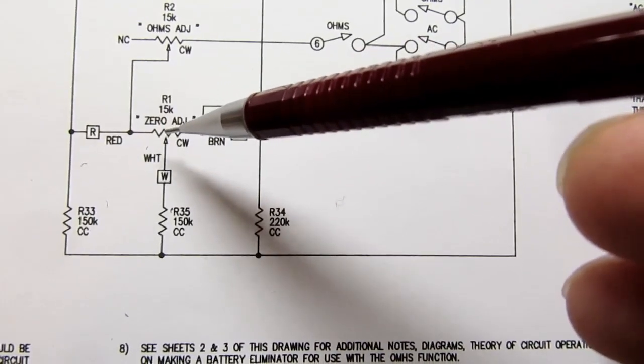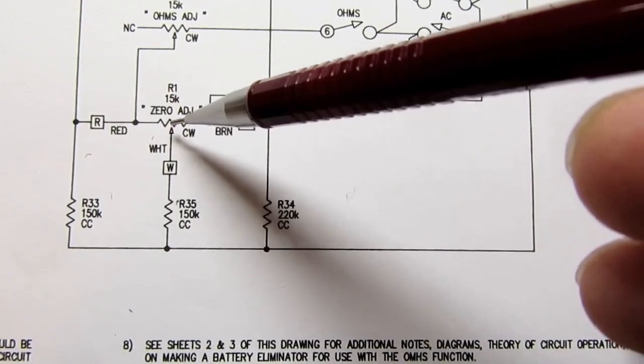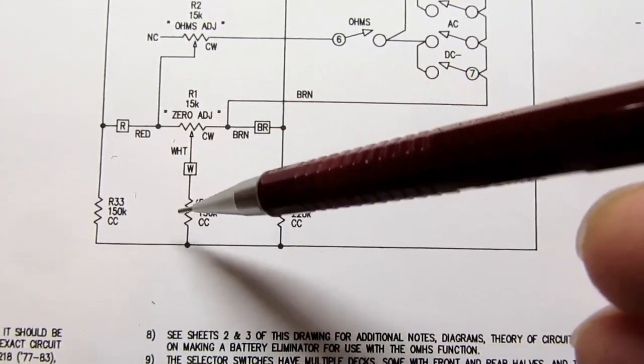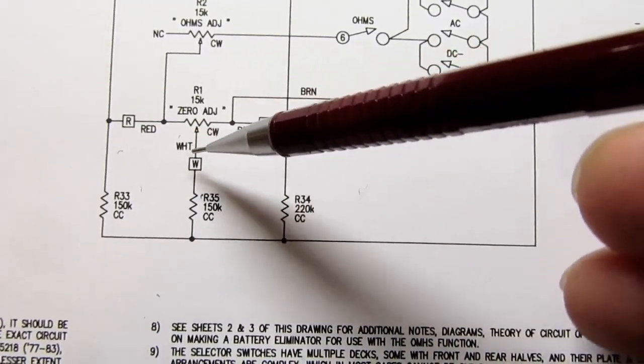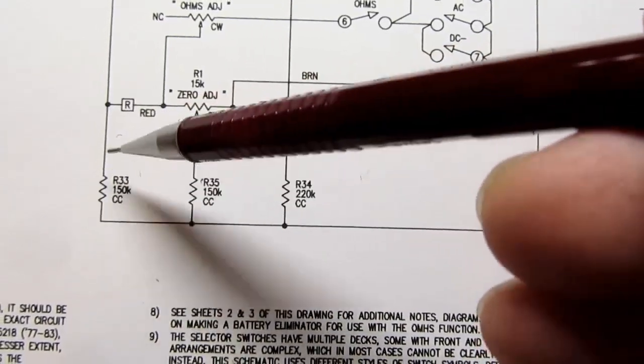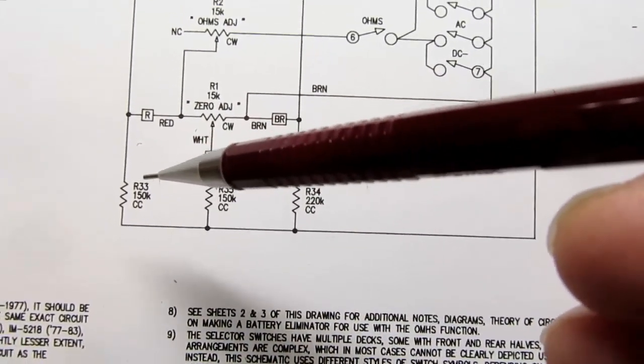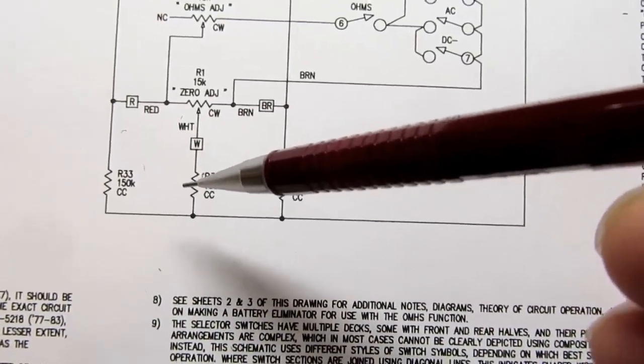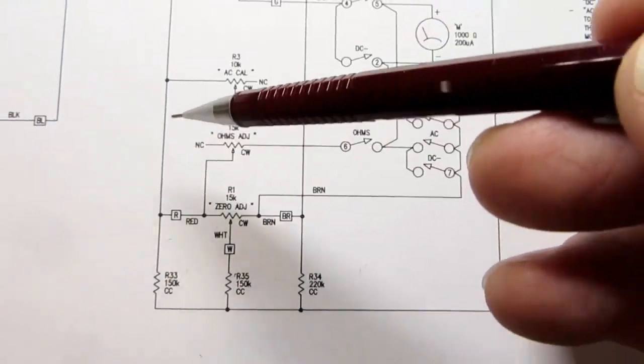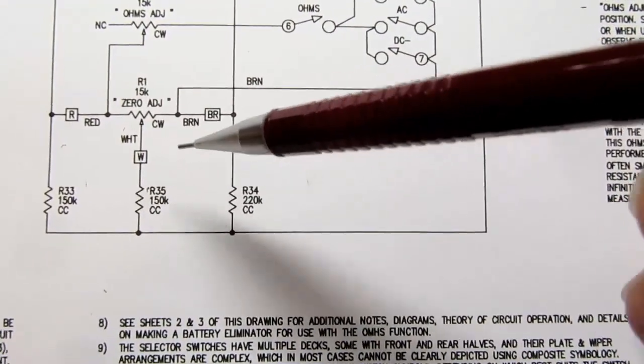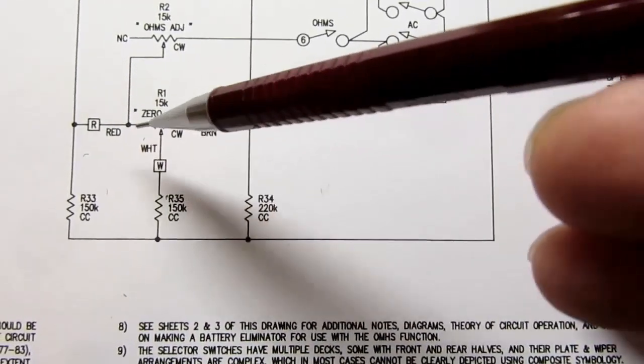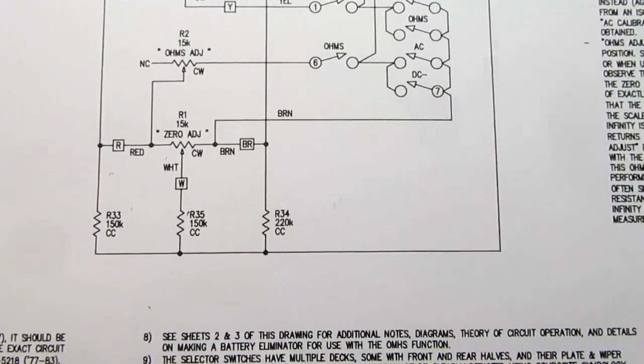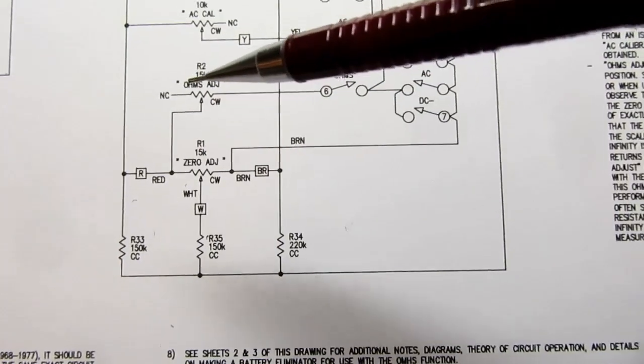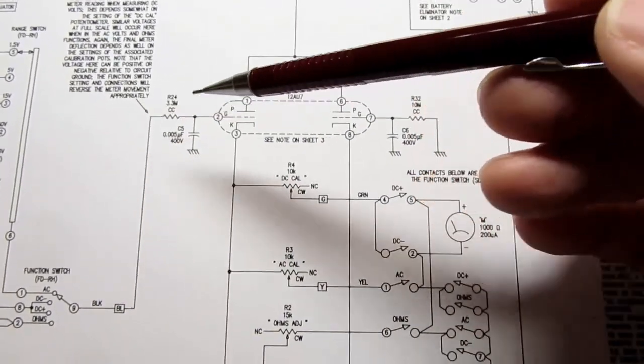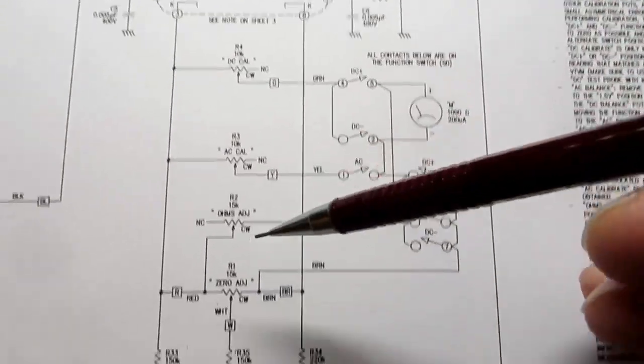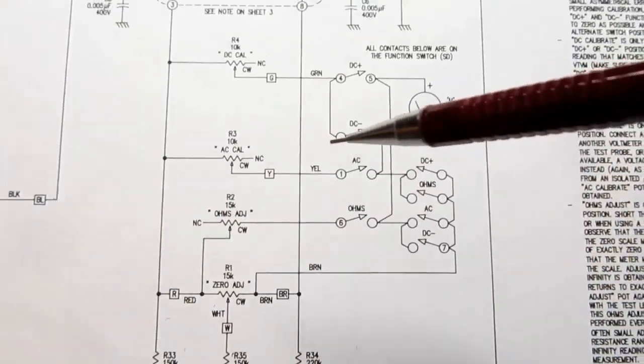So if this zero adjust potentiometer is in the middle of its position, you can think about it as a resistor here and a resistor here, and then a resistor here and the same resistor here. And those are essentially in parallel with these resistors, and we know that if you have two resistors in parallel and you vary one of them, that varies the overall resistance, and therefore it would change that part of the bridge resistance. And while you're increasing one side, you're decreasing the other because of moving this pot around. So that's the way we can skew the bridge, and by skewing it we can get it balanced. When you know you have 0 volts here, and you know that means you should have a 0 reading on the meter, you can adjust this until you get that, and then the bridge is balanced.